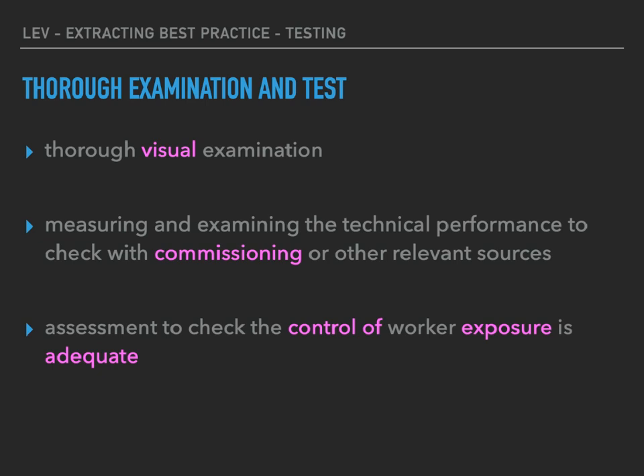The test requires a lot of information to be gathered and documented, and there's a list of this found in HSG 258. The report document will run into several pages. A lot of that information, as the owner of a system, you don't really need, but you do need the executive summary. You need to know if there are any issues, and good practice would be to put that on the front page. The pressures, flow rates and velocities in the system aren't really an issue unless they're not right, and that should be within the executive summary.